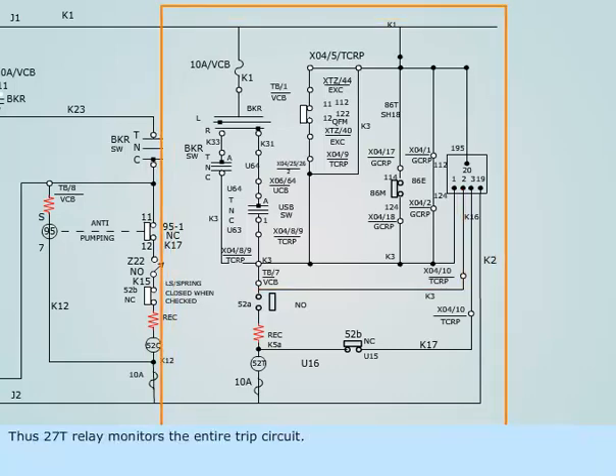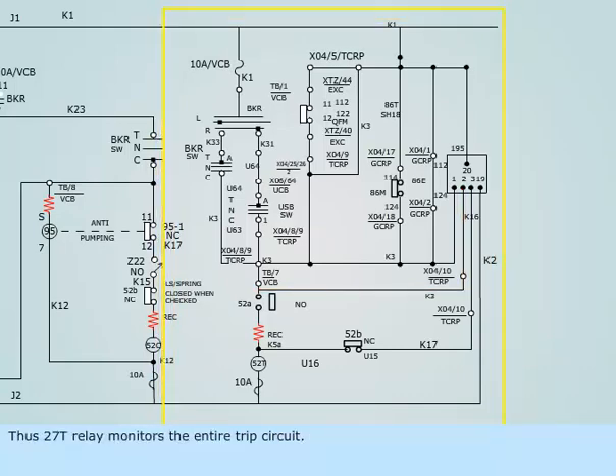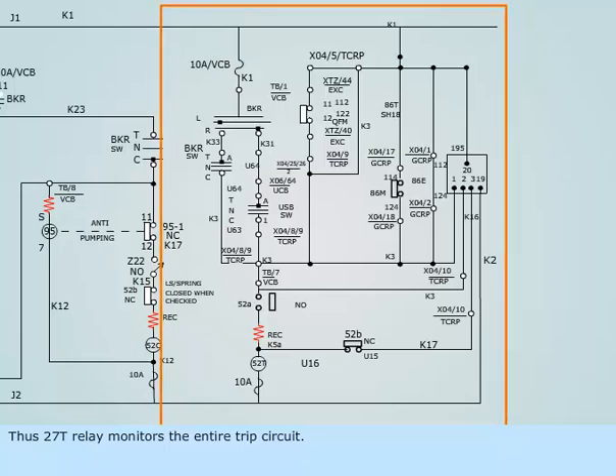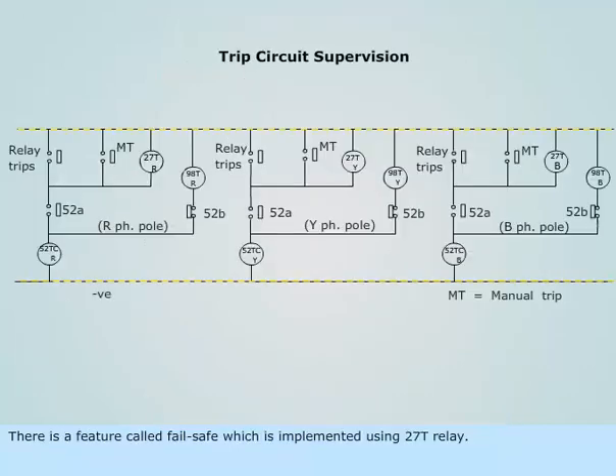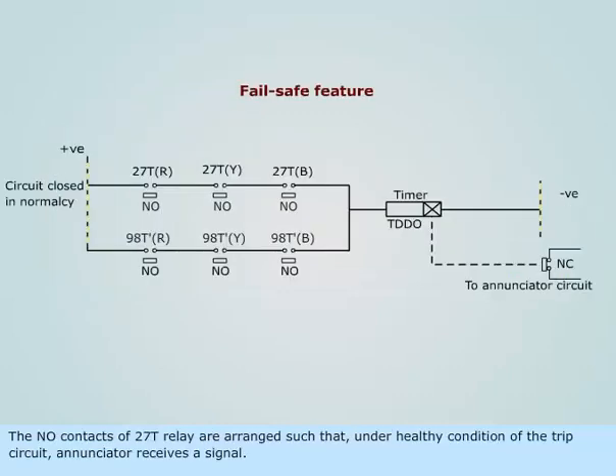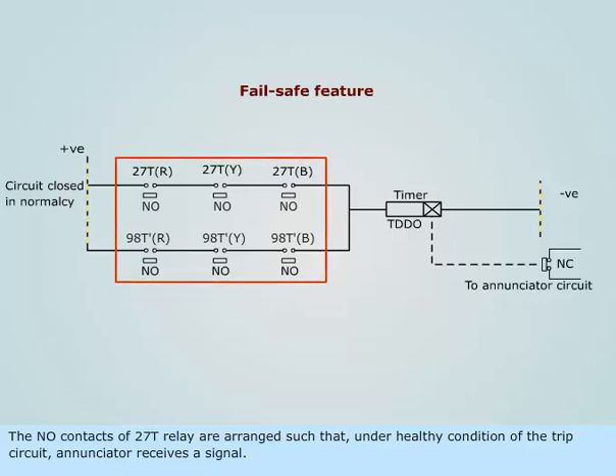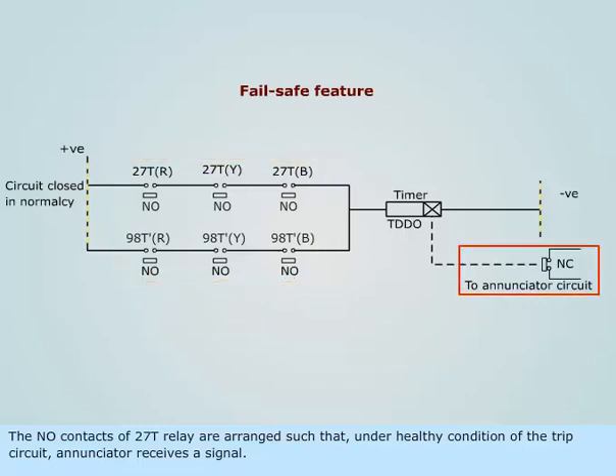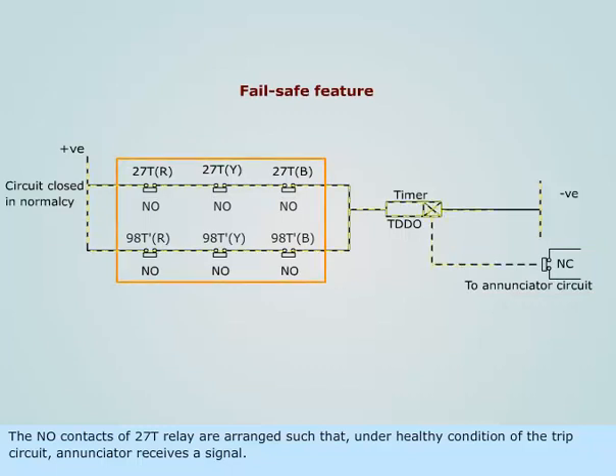Thus, 27T relay monitors the entire trip circuit. There is a feature called fail-safe which is implemented using the 27T relay. The NO contacts of 27T relay are arranged such that under healthy condition of the trip circuit, the annunciator receives a signal.